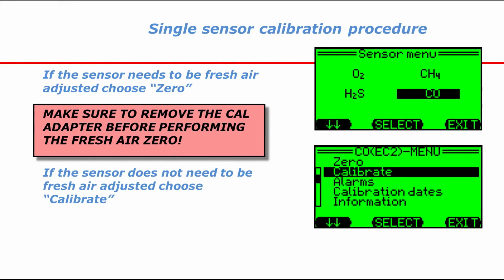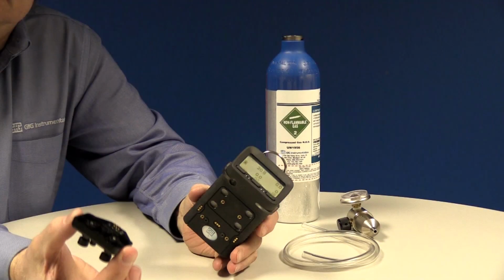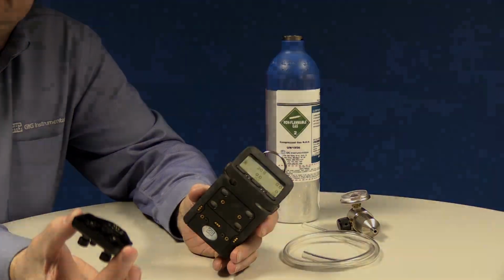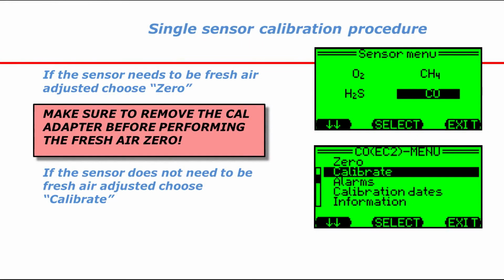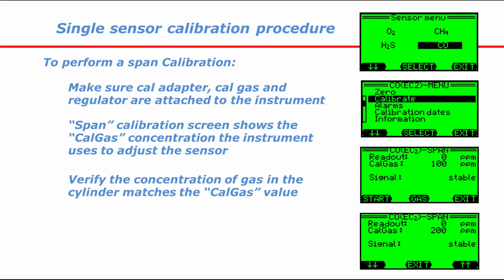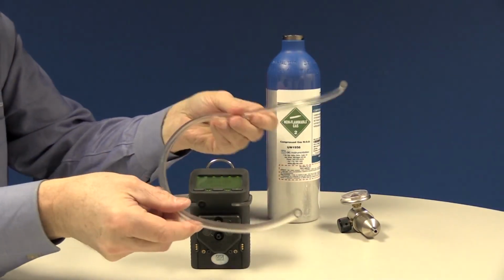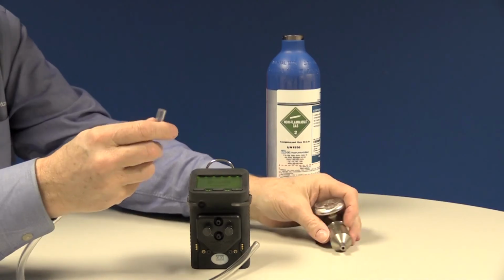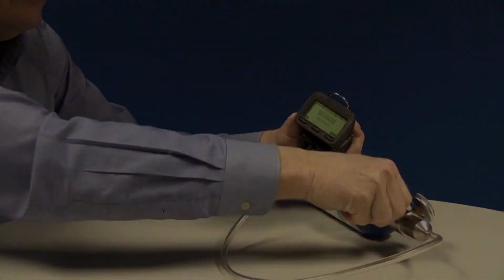If the sensor needs to be fresh air adjusted, choose Zero. Make sure to remove the calibration adapter before performing the fresh air Zero. If the sensor does not need to be fresh air adjusted, choose Calibrate. The Calibrate screen shows the concentration of gas the instrument is expecting you to use. Make sure the cylinder of gas has the same type and concentration of gas that the instrument is expecting. Attach the calibration adapter and tubing to the regulator and cylinder of gas. Open the regulator to begin flowing gas and press Start.